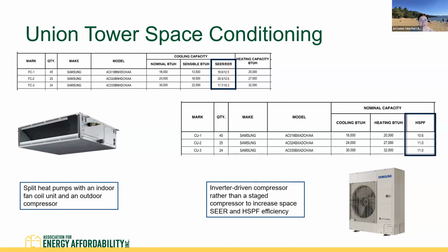All right, so let's take a look at Union Tower. What we see here is a unitary split ducted heat pump system. So for each apartment, there is an indoor fan coil unit and an outdoor compressor that are connected by a refrigerant line set.